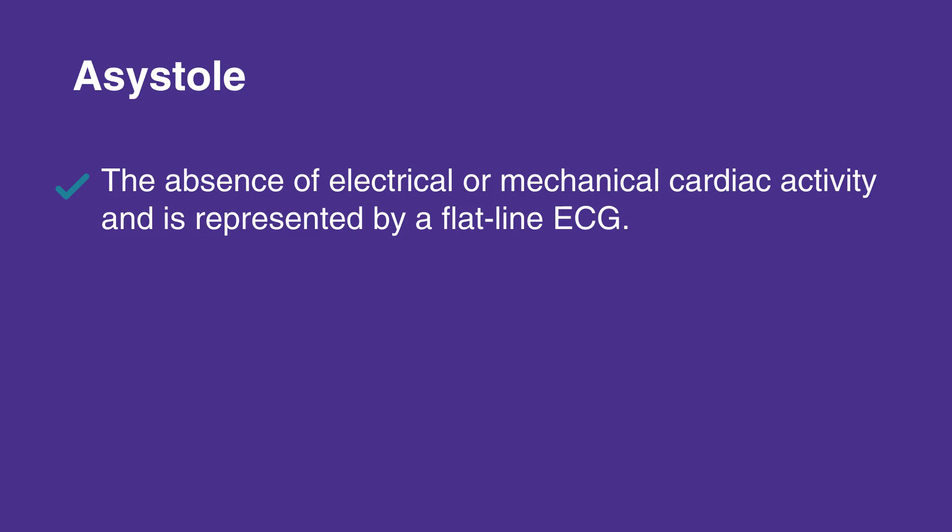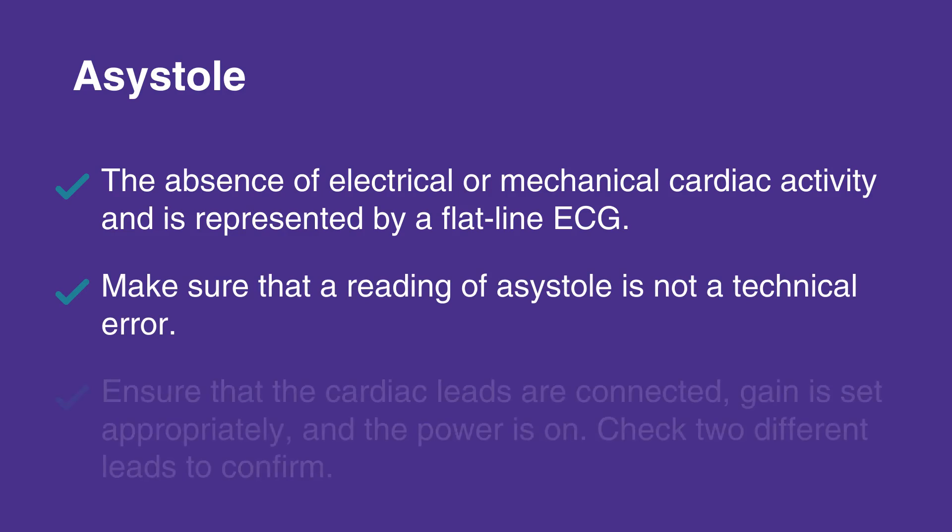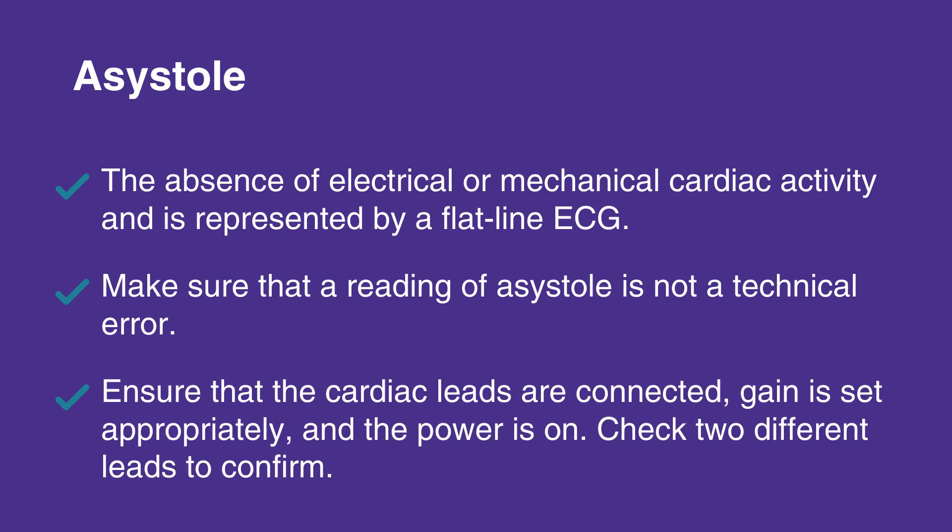Make sure that a reading of asystole is not a technical error. Ensure that the cardiac leads are connected, gain is set appropriately, and the power is on. Check two different leads to confirm.